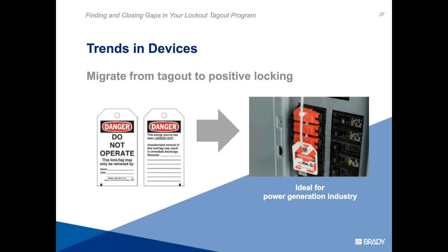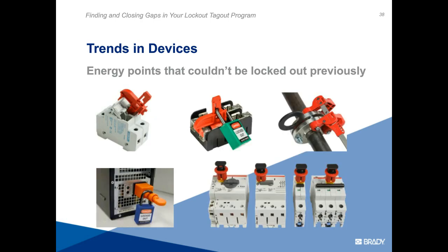We're also seeing more applications that can be locked out where previously this wasn't possible. In the photo above, on the left is a fuse circuit breaker lockout where the device blocks and prevents a fuse from actually being inserted and the door closed. The top middle image is of a terminal block to keep the terminals physically separated and locked out.